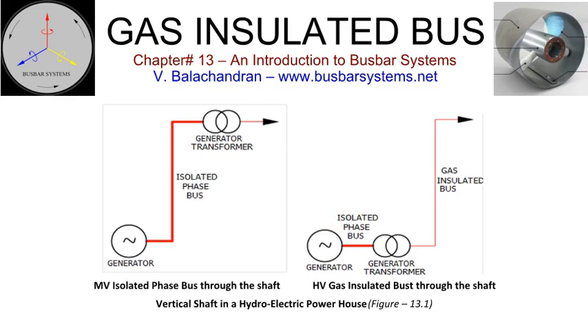bus carrying a large magnitude of current at medium voltage. The isolated phase bus will run through the vertical shaft. The cross-section of the shaft has to be large to accommodate the isolated phase bus and space for routine maintenance and evacuation of heat generated by the isolated phase bus. The generator transformer can be located underground close to the terminals of the generator, and a gas-insulated bus carrying a smaller magnitude of current at high voltage can be run through the vertical shaft and connected to the transmission line.